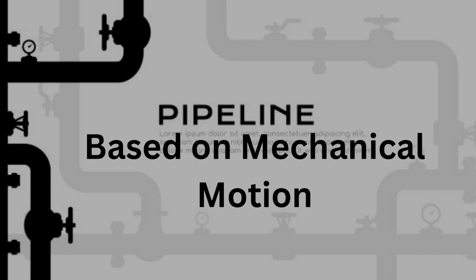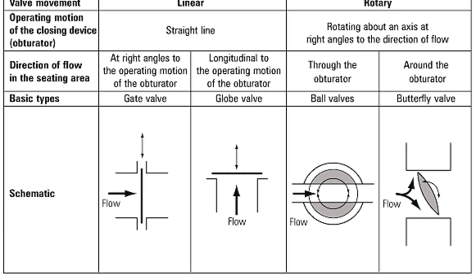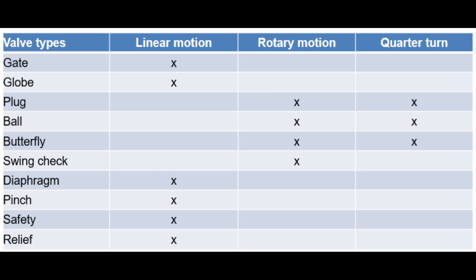Based on motion, valves are majorly classified into three types: 1. Linear motion valve, 2. Rotary motion valve, 3. Quarter turn valves. Linear motion valves are those in which the closure member — as in gate, globe, diaphragm, pinch, and lift-check valves — moves in a straight line to allow, stop, or throttle the flow. Rotary motion valves are those where the closure member travels along an angular or circular path, as in butterfly, ball, plug, eccentric, and swing-check valves. Quarter turn valves are rotary motion valves that require approximately a quarter turn (0 through 90 degrees) of the stem to go from fully closed to fully open, or vice versa.